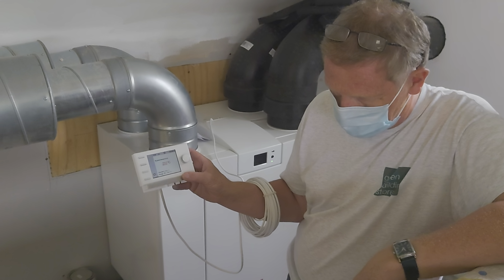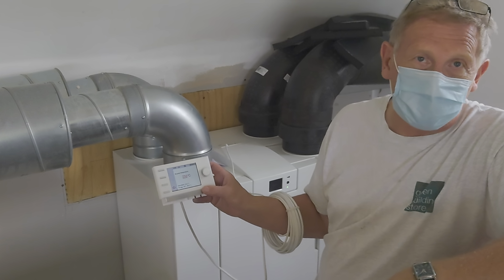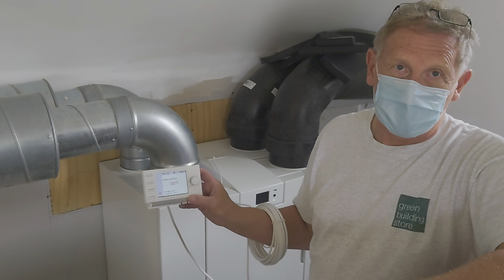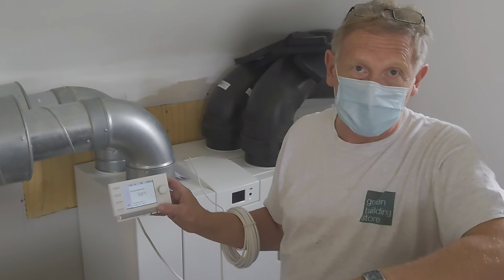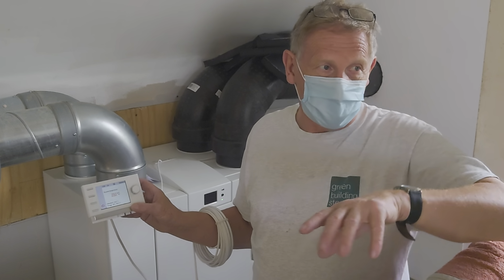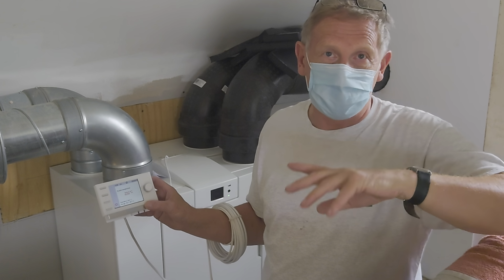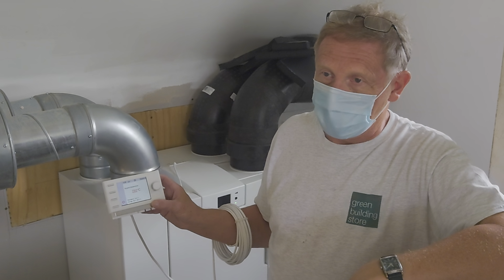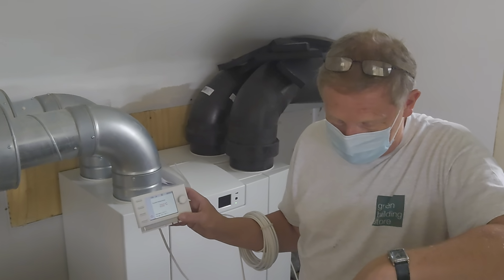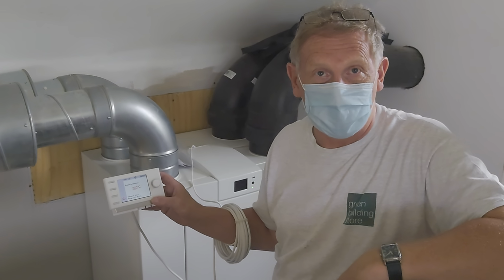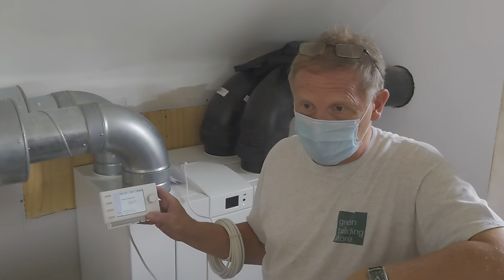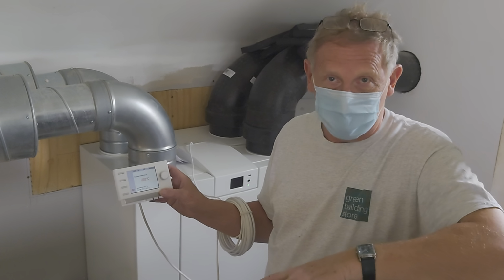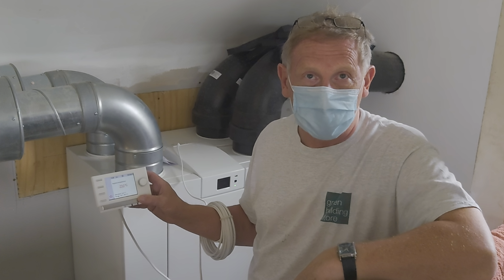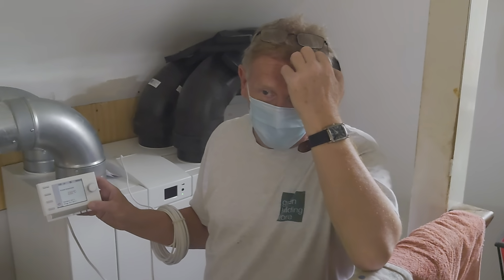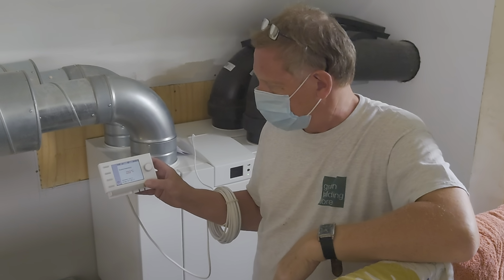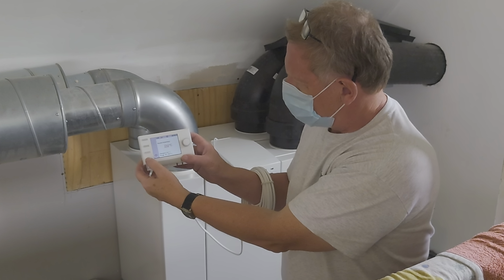What heating have you got in the house? Underfloor, just downstairs. Okay, and what are you likely to set your thermostats to in winter? 21. So your heating system is going to be trying to heat up to 21. Bearing in mind that on top of that you might get some incidental heat gains from cooking, fridges, TVs, bodies, and a wood stove. Not sure we'll need to use that, but on a very cold day it could easily be creeping up above 23 degrees in winter, if you've got a wood stove lit. So as soon as that goes above 23, ventilation will start dumping the heat to outside. Which is fair enough, if you're going above 23 it might be a bit uncomfortable. Okay, so that was the bypass temperature.